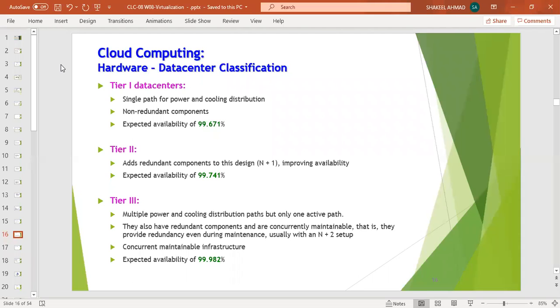Next type are tier 3 data centers: multiple power and cooling distribution paths, but only one active path. There are paths and sources available to provide electric power and cooling, but only the active path is used and in service for the data center. Tier 3 data centers have redundant components and are concurrently maintainable, meaning they provide redundancy even during maintenance, usually with an N plus 2 setup. Tier 3 data centers have concurrently maintainable infrastructure, and expected availability of service is 99.982%.